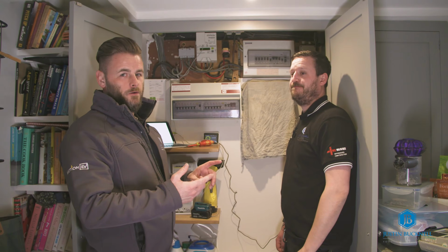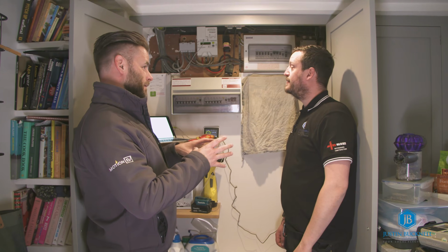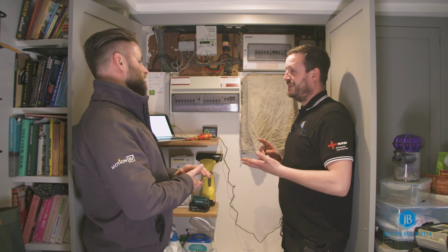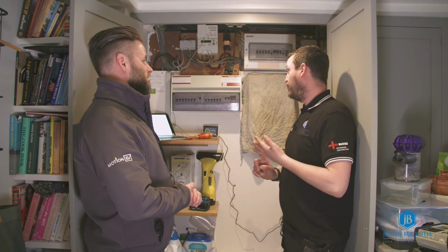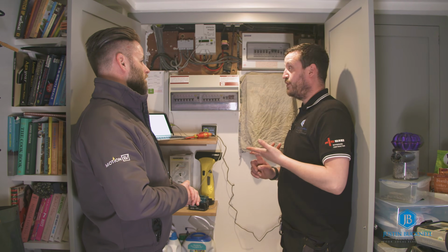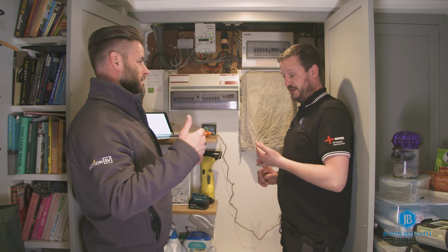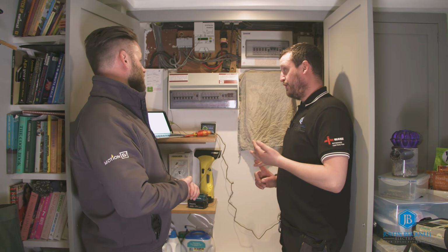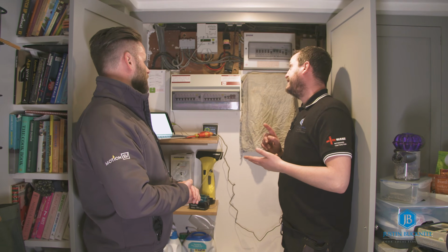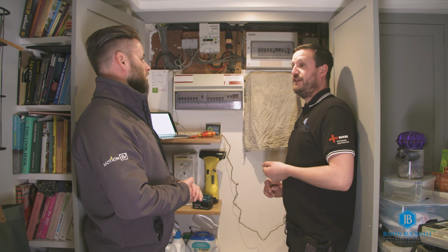So we've got Adam here now. So Adam, what is it you like to check off first when you start an EICR? Main earth, find the rod, because this is obviously a TT system. Yeah. Your oil bond, water bond, gas bond. Yeah. So this particular property's got oil, so there's only going to be an oil bond. Yeah, and look for the water bond, and then any visible observations around the house, so then we can start filling the test sheet out.